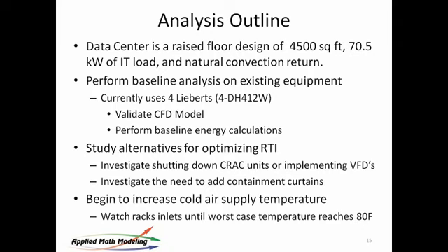And the process we'll use is to validate the model, perform baseline energy calculations, and then begin to modify by first going for RTI, trying to get the air in place. And then we're going to use some containment to optimize the airflow. And then we're going to walk up the cold air supply temp and see how far we can get. This particular model is a fairly straightforward data center. This one's DX based, so our ability to move the RTI number a long distance gets constrained by the fact that they're DX units themselves.